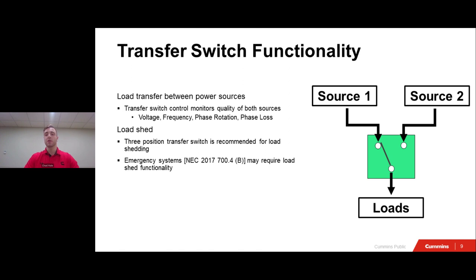And then lastly, we have something called load sequencing. This is when you have a system with multiple automatic transfer switches within your system. And within the system, you can adjust the transition delays within your transfer switches to ensure that your emergency loads are receiving power first. And then as you move into those delays and those other transfer switches, your more non-critical, non-emergency loads will be receiving power from those transfer switches.